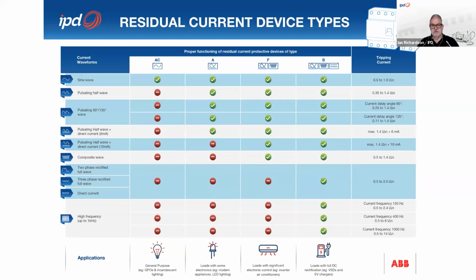The type AC is the most basic version of an RCD which is available. This is able to detect a residual fault with a standard sinusoidal waveform. With the introduction of electronics, we saw a lot of non-sinusoidal waveforms appear, and the type AC couldn't necessarily detect that. So we needed a more advanced device called a type A. The type A is capable of detecting faults with rectified or pulsating half waves, as well as direct currents superimposed on the sine wave up to 6 milliamps.